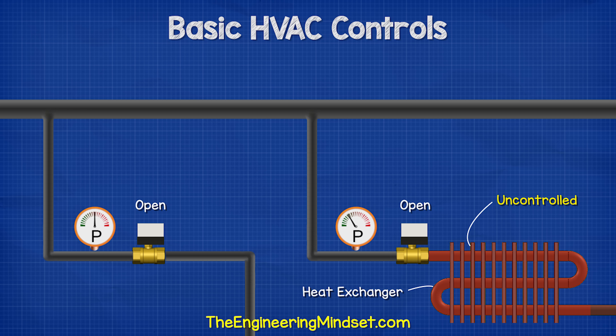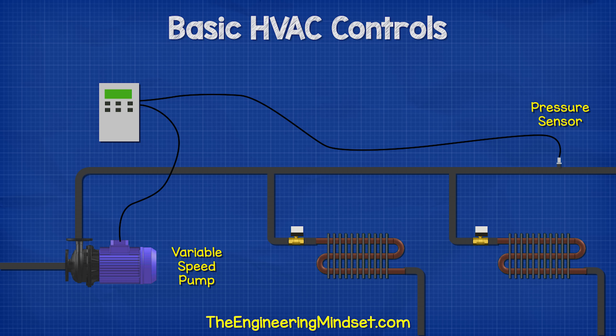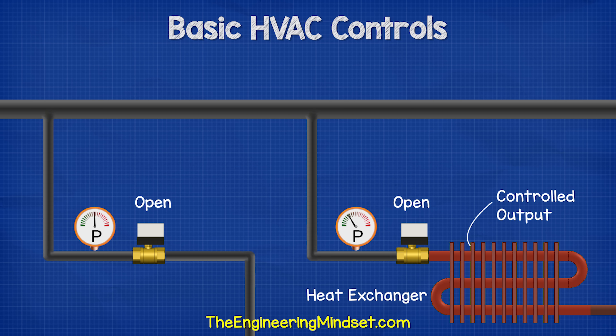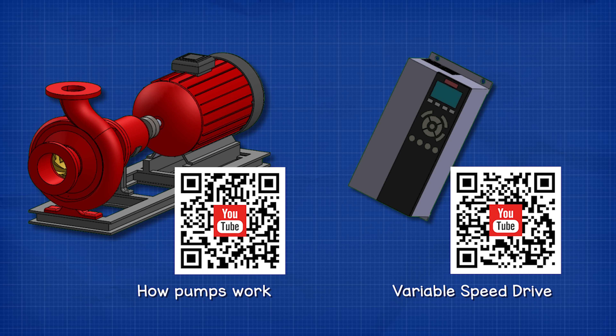To overcome this, we could install a pressure sensor and a variable-speed pump. As the valves open and close, the pump changes speed to try and maintain a constant pressure and thus a constant flow rate through the radiators, regardless of when another valve opens or closes. We have covered how variable-speed drives work and also how pumps work in our previous videos — I'll leave a link in the video description below.